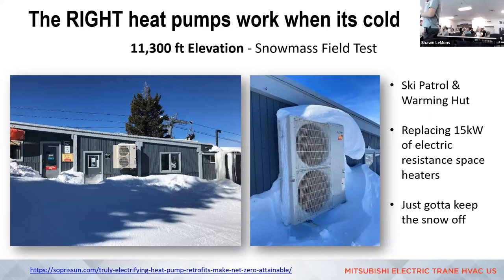We like that. What was a problem, and that's what you see in the right-hand photo, is that they didn't clear the snow away properly enough. When they got 5.5 feet of snow in 9 days, it just got inundated with snow and couldn't keep up. So yes, you've absolutely got to keep the snow off of these things. You have to be thoughtful about these exceptional products because they're not perfect. They will defrost themselves, but they're not going to clean the snow off from around them themselves.